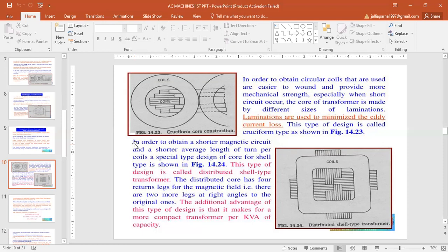The distributed core has 4 return legs for the magnetic field. That is, there are 2 more legs at right angles to the original ones. The additional advantage of this type of design is that it makes for a more compact transformer per kVA of the capacity.